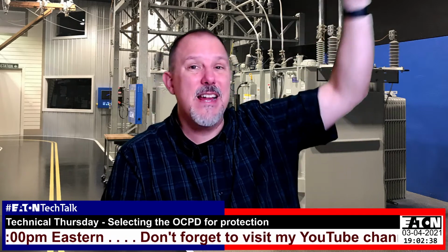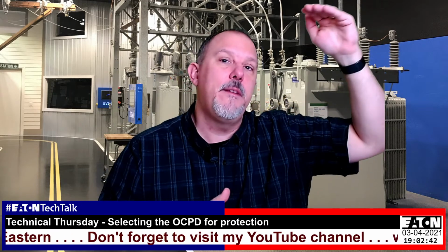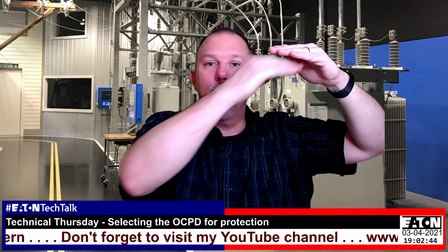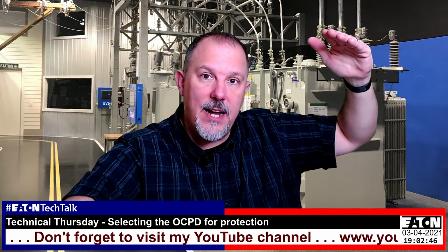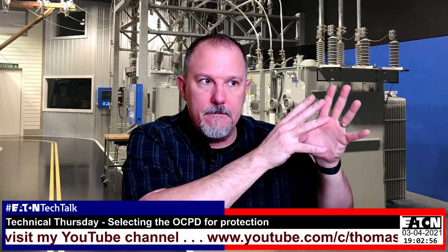Why? Because I've got a load side lug that's not protected. It's outside of the zone of protection. I have a line side lug that's outside of the zone of protection. If I put ARMS on the main in that equipment, I'm protected all the way down through the load side, but I still have that vulnerability on the line side, but now I have barriers which will reduce the likelihood. It's all about likelihood and severity. I can reduce the likelihood on the line side.